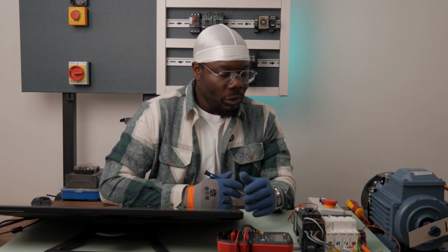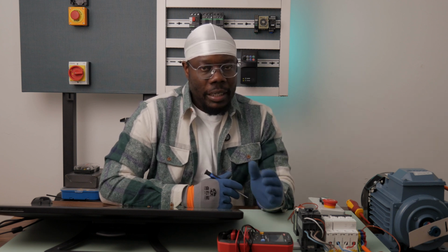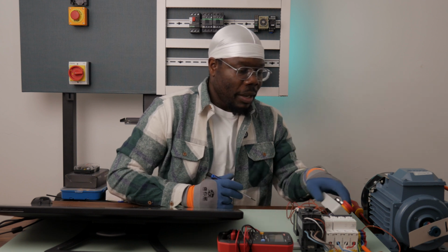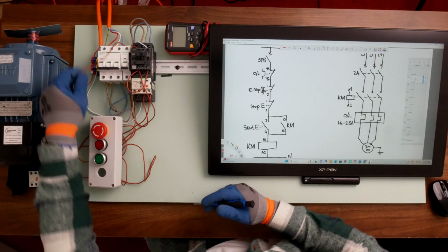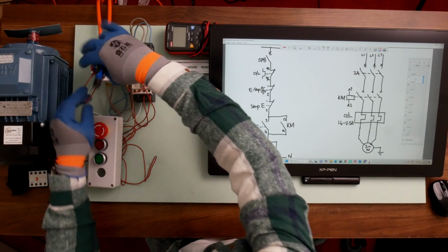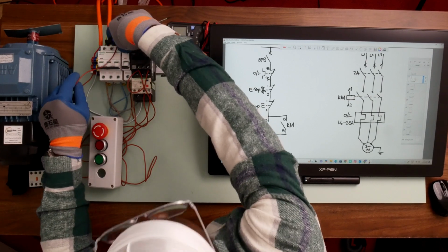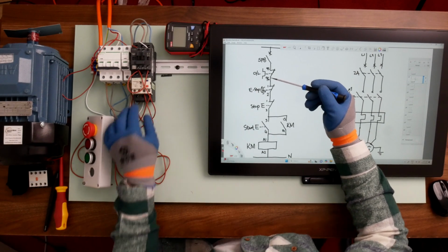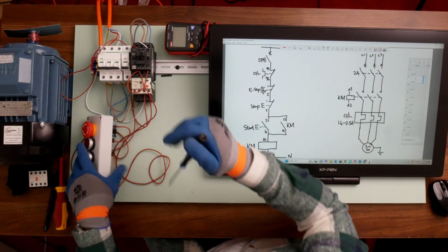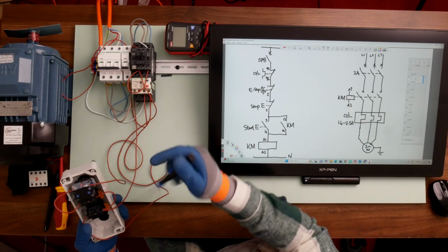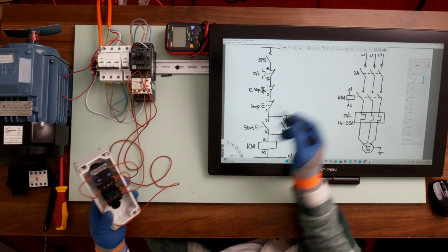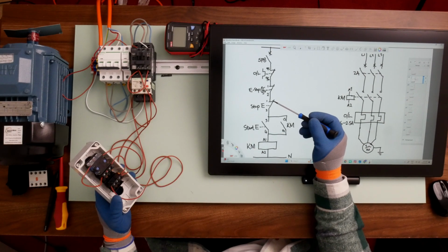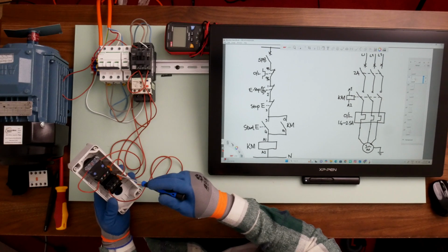So I'm just going to quickly trace through my control wiring just to make sure that I've done the right thing. My first connection here is coming from my supply, which is the red terminal here. It's going to the top of my control breaker. Then it goes into 95, just like on our circuit diagram here. Then from 96, it goes to 1 on our e-stop here, just like here. And then my e-stop is looped to 1 on my stop button. And then from my stop button, I go to the start button.